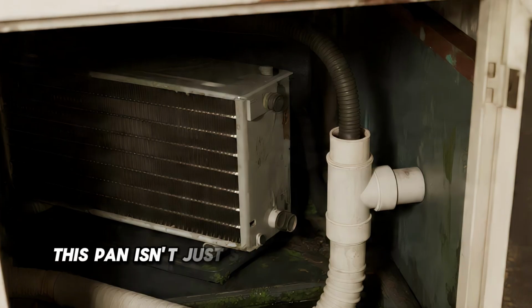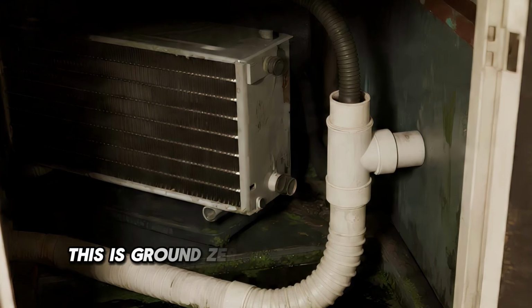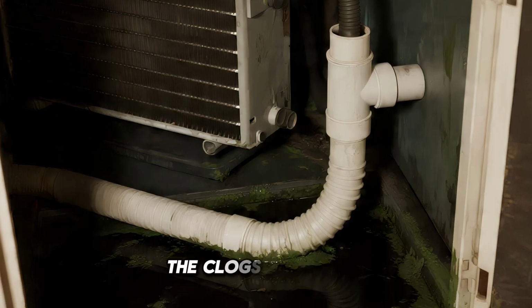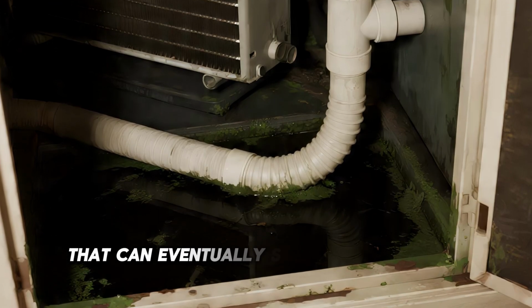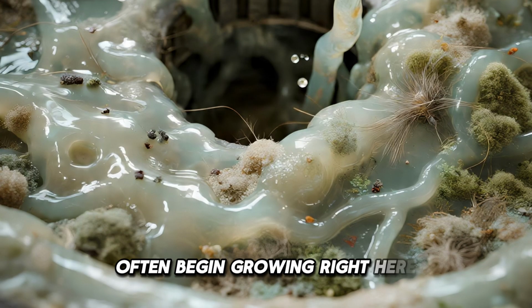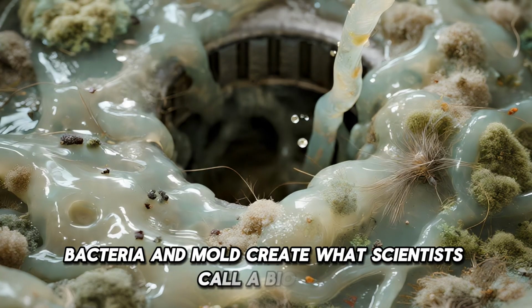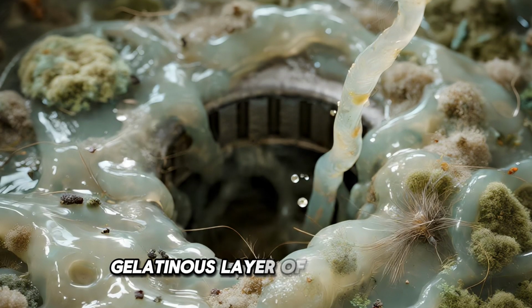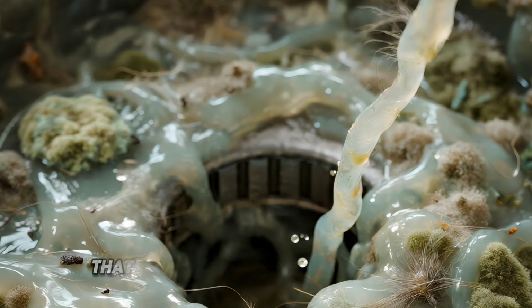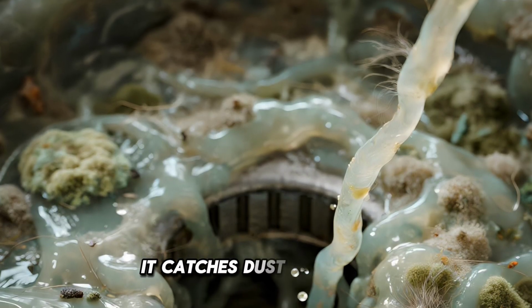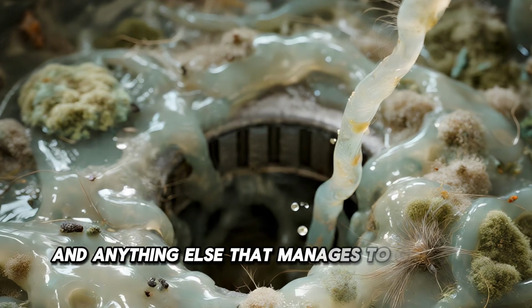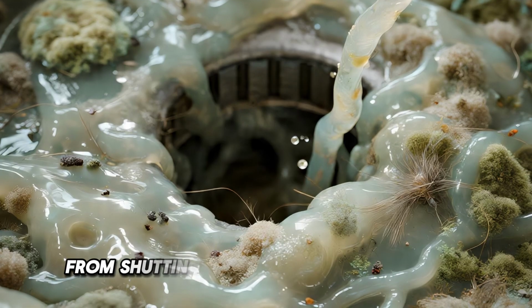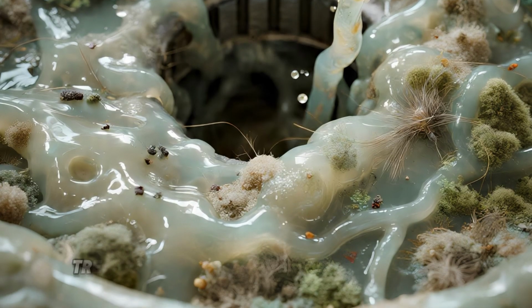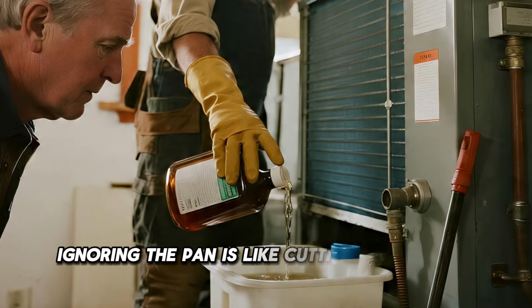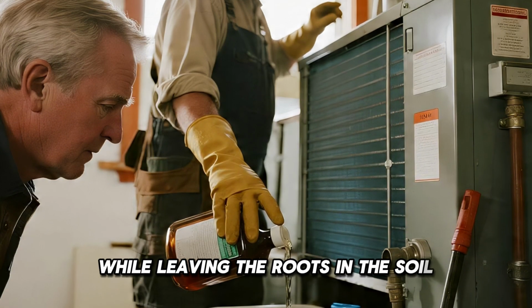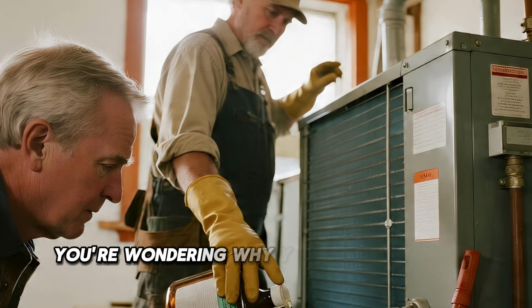And that means this pan isn't just some secondary drainage component. This is ground zero. This is the biological factory. The clogs, bad odors, and backed-up drain lines that can eventually shut down your air conditioner often begin growing right here. Bacteria and mold create what scientists call a biofilm, a thick, slippery, gelatinous layer of living slime that sticks to the surface of the pan. That slime then works like a magnet. It catches dust, pet dander, hair, and anything else that manages to get past your filter. If you want to prevent clogs from shutting down your air conditioner, you have to go after the source. Treating the drain pipe while completely ignoring the pan is like cutting the top off a weed while leaving the roots in the soil. It grows back, and 6 weeks later you're wondering why your treatment didn't work.